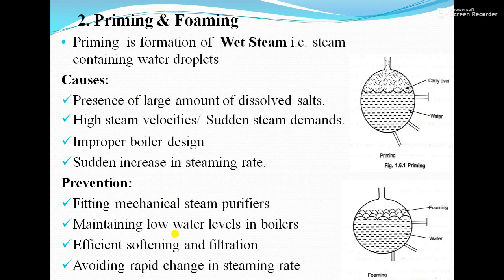Next is priming and foaming. Priming is the formation of wet steam — that is, steam containing water droplets. Due to violent and vigorous boiling, wet steam forms. The causes are: first, presence of a large amount of dissolved salts; second, high steam velocities and sudden steam demands; third, improper boiler design; and fourth, sudden increase in the steaming rate.